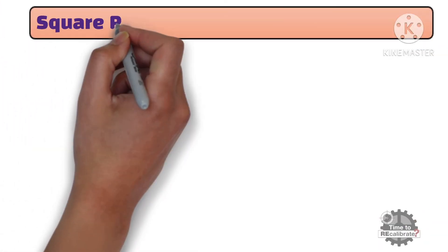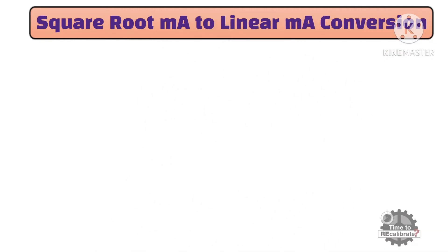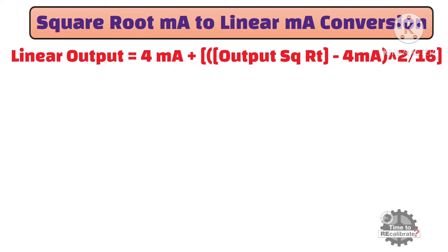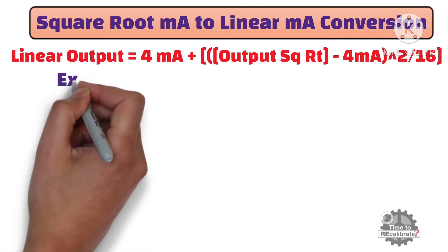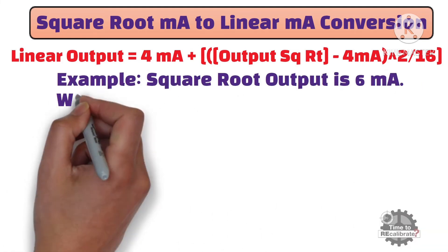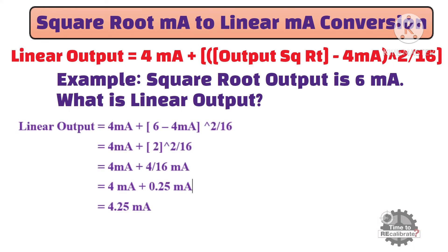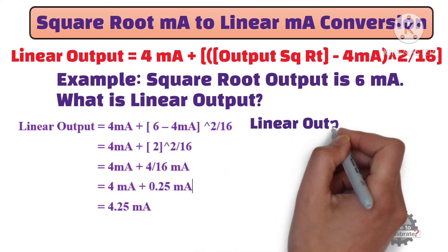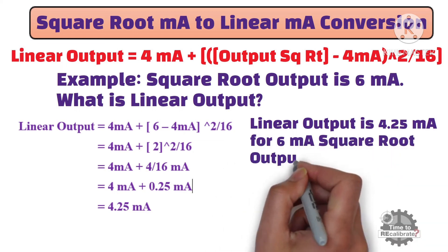Now, let's try to understand square root milliampere to linear milliampere conversion. This is a standard formula for square root milliampere to linear milliampere conversion. You just need to put the square root output milliampere value, and it gives the linear output milliampere value. For example, if the square root output is 6 milliampere, what is the linear output? Put 6 milliampere into the formula and do the simple math calculation. All values remain the same except the square root milliampere value. The result is 4.25 milliampere — in other words, the linear output is 4.25 milliampere for a 6 milliampere square root output.